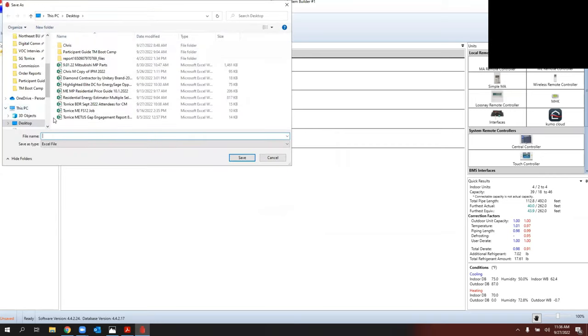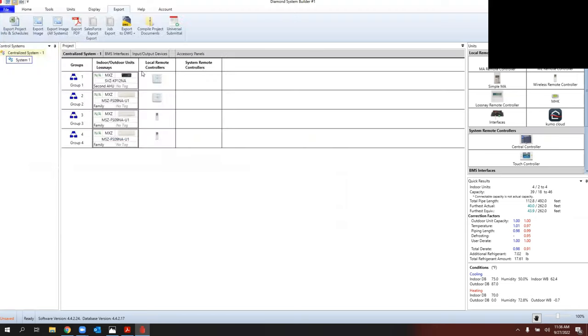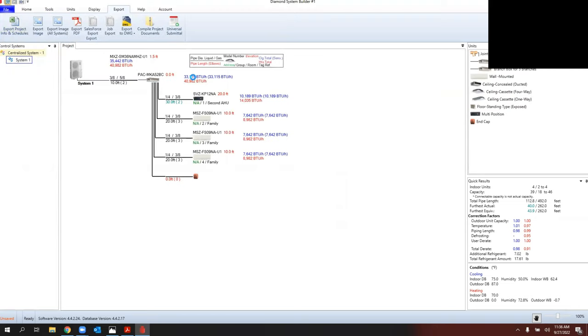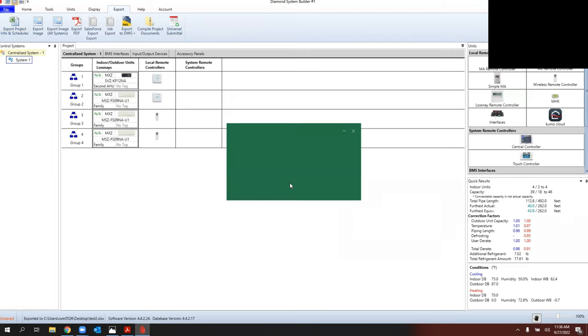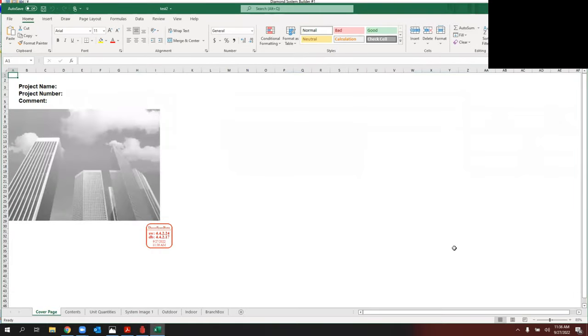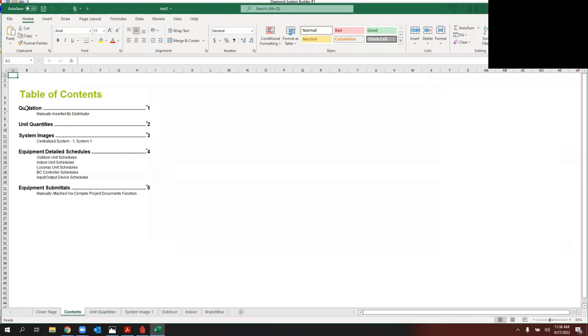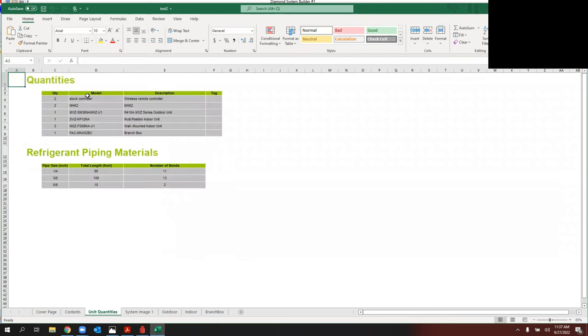I'll export using Project Info and Schedules — I recommend leaving all options checked. When I hit OK it opens an Excel file. Each tab is a separate page. If you typed in a project name, number, or comments they show up on page one. The Contents tab tells you which tab contains each piece — unit quantities, system images, detailed schedules, and submittals for everything selected. Under Unit Quantities, it lists all the Mitsubishi equipment selected, pipe lengths, number of bends needed — it does all the calculations for you.